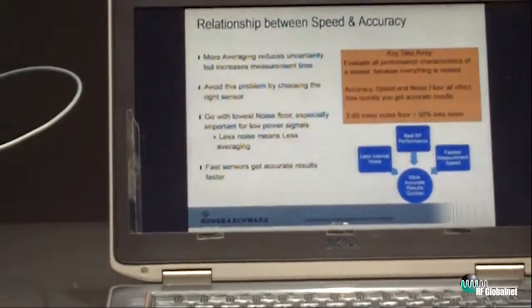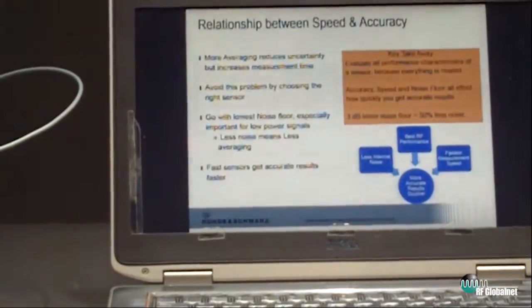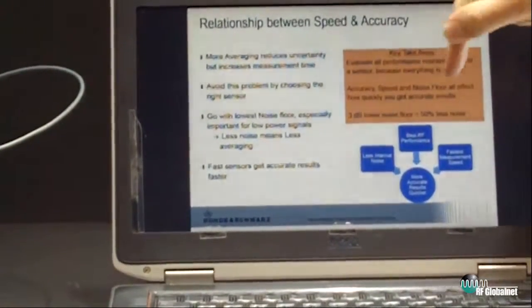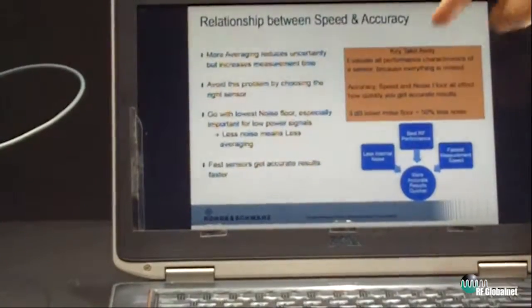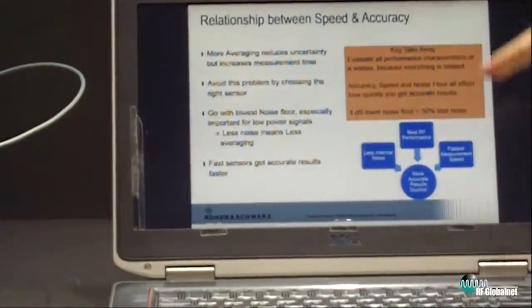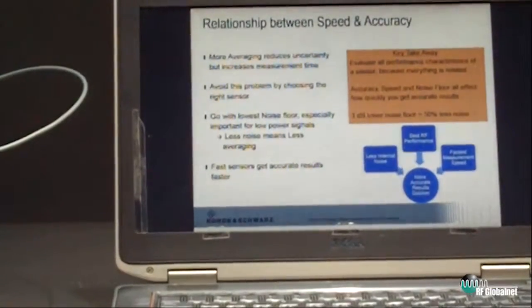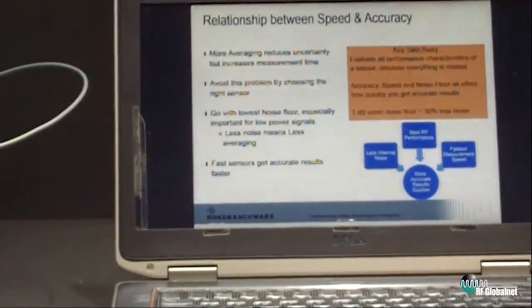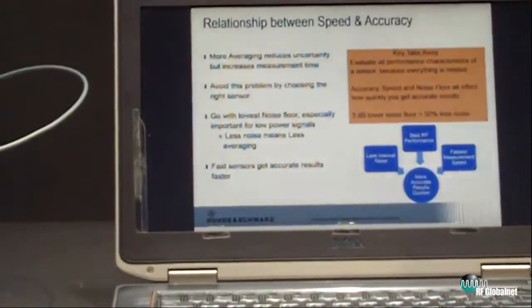Go for a sensor with the least internal noise, with the best RF performance in terms of uncertainty numbers, and with a fast measurement speed. When you combine all three of those together, you're going to be able to get accurate results quickly. And that is the key for any power sensor measurement you're making.